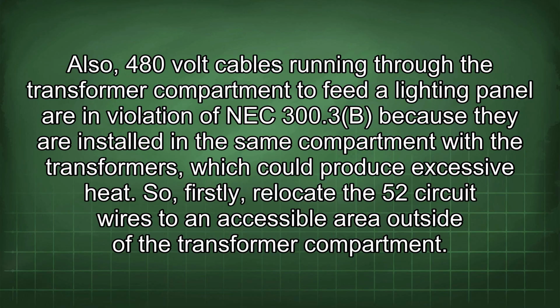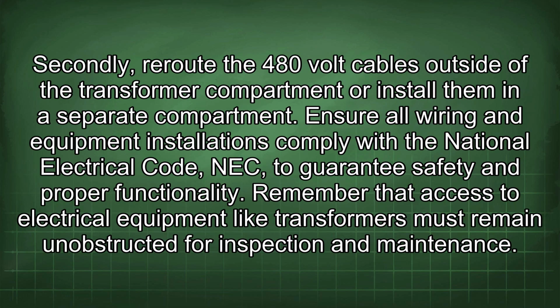So, firstly, relocate the 52 circuit wires to an accessible area outside of the transformer compartment. Secondly, reroute the 480-volt cables outside of the transformer compartment or install them in a separate compartment. Ensure all wiring and equipment installations comply with the National Electrical Code (NEC) to guarantee safety and proper functionality. Remember that access to electrical equipment like transformers must remain unobstructed for inspection and maintenance.